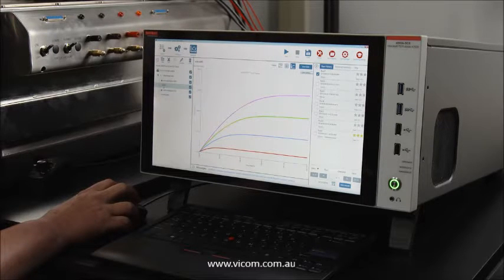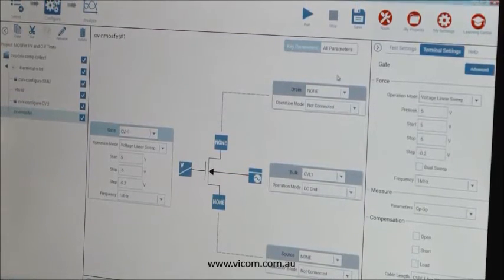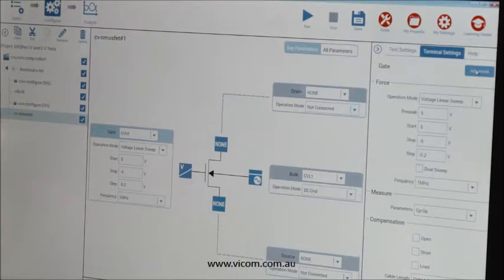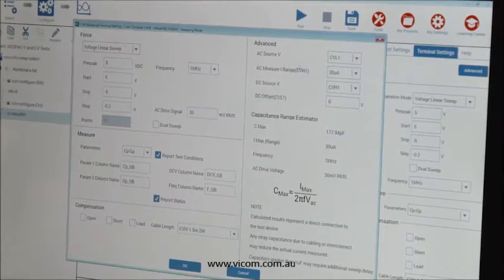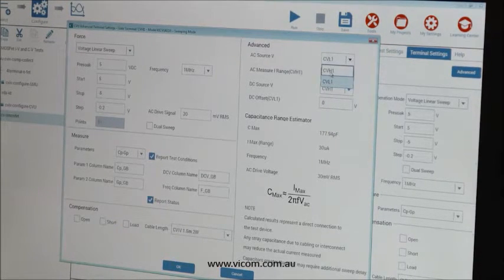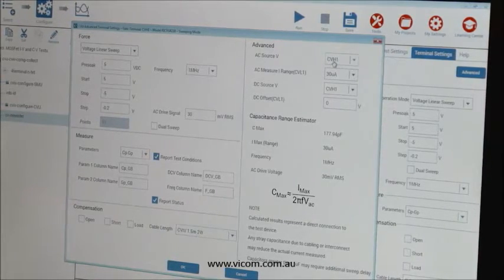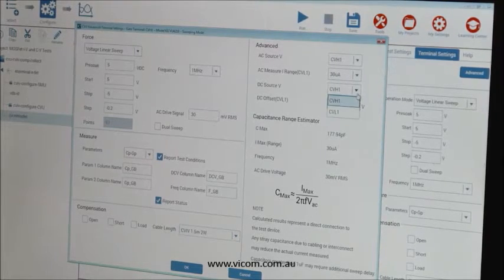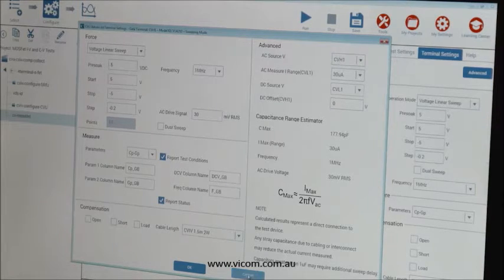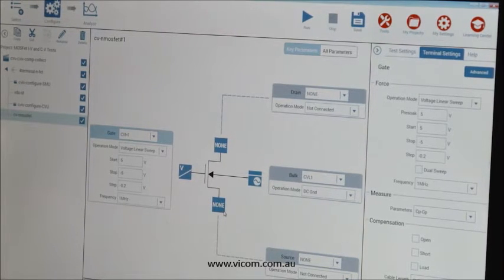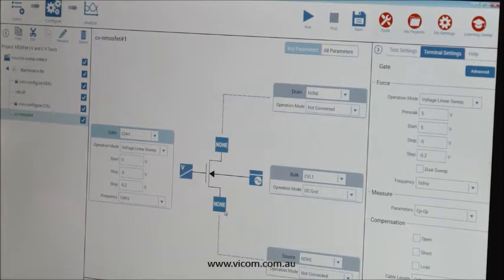Another tip: when you're making an AC measurement and you're noticing that your readings are very noisy, there's a very simple way to check your test setup. In the software, under the CV test, you can go to the terminal settings and open the advanced tab. This area allows you to switch where your AC source is measured and where your DC source is applied, with just a simple mouse click. You can see here I've switched from CV high to CV low for where we measure the AC, and similarly for the DC. What this does is you don't have to re-cable or reconfigure your test setup — you can easily switch to the least noisy terminal with a click of a mouse.